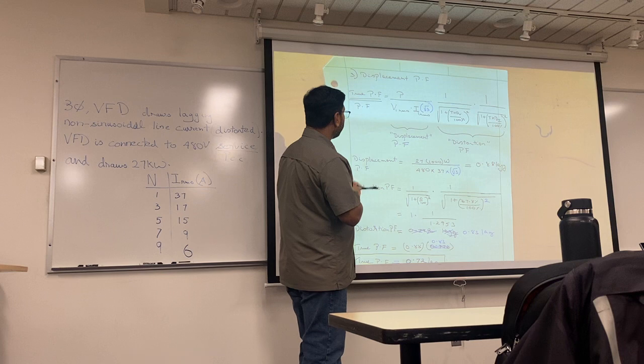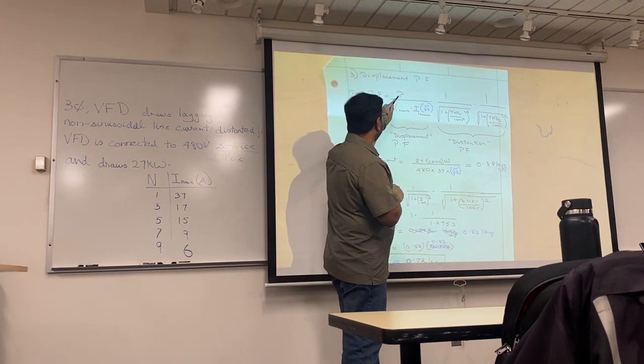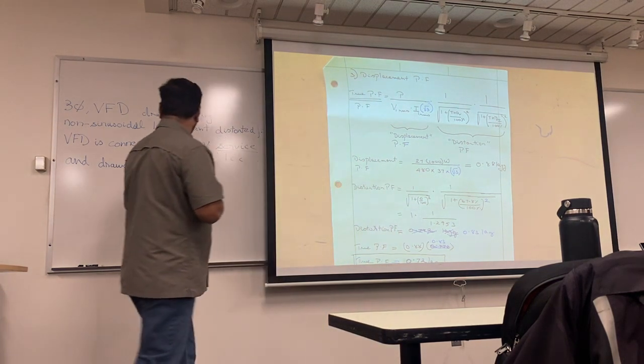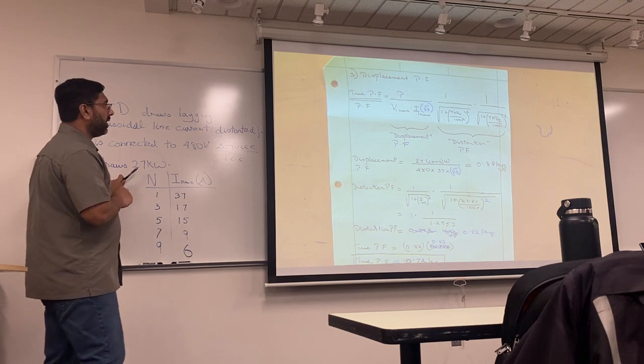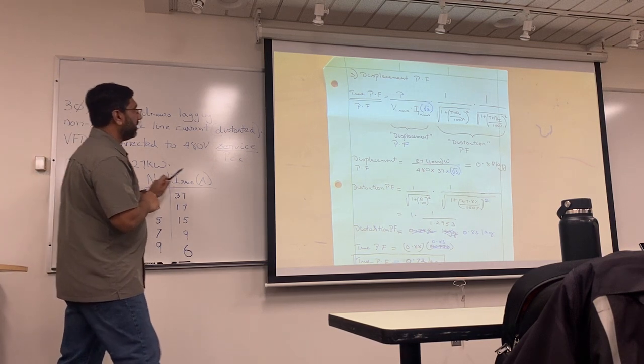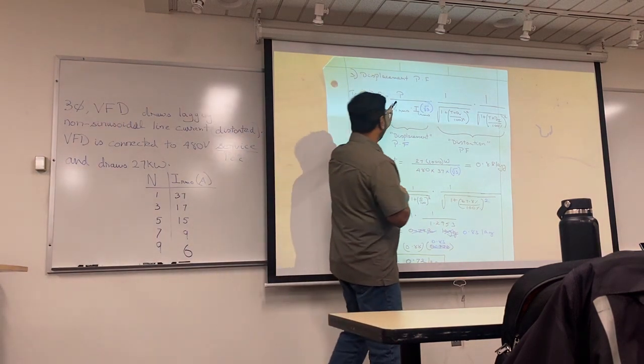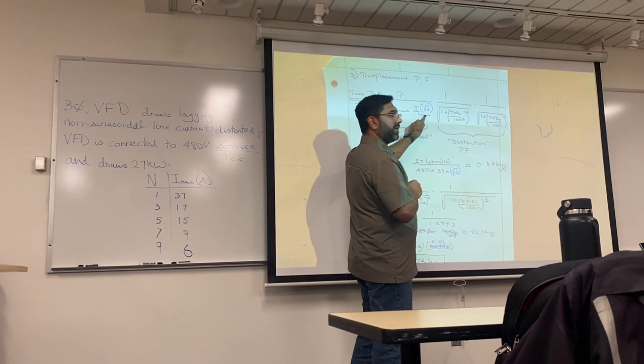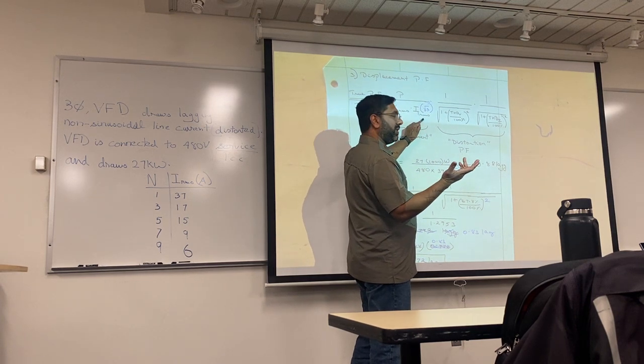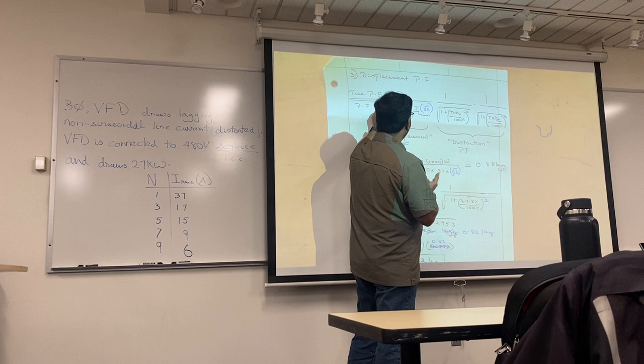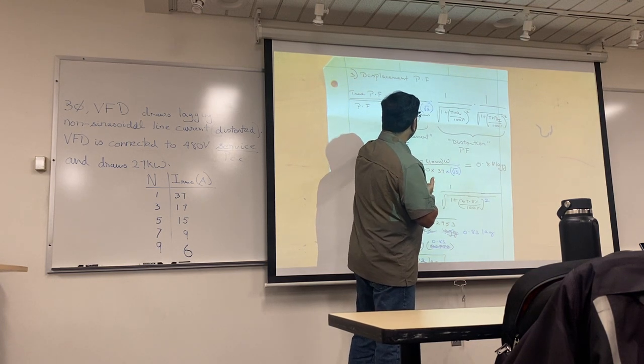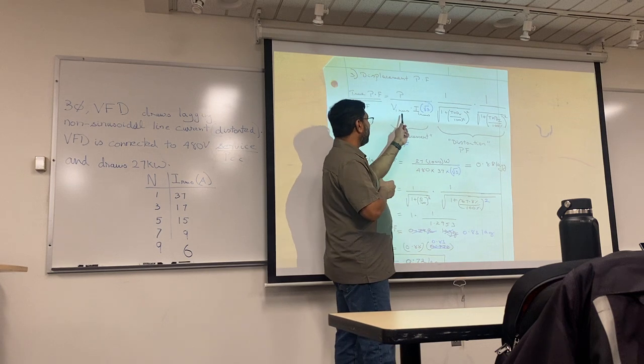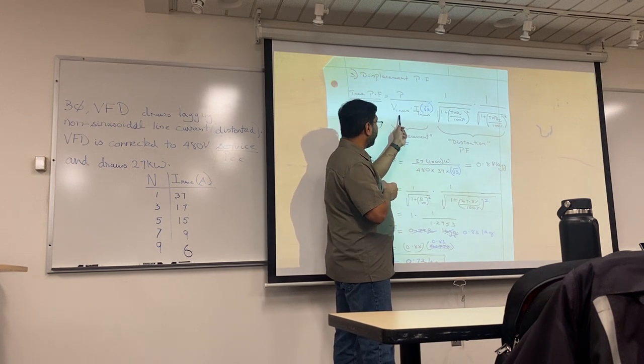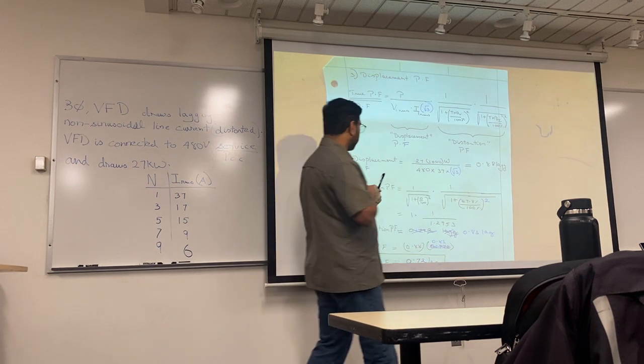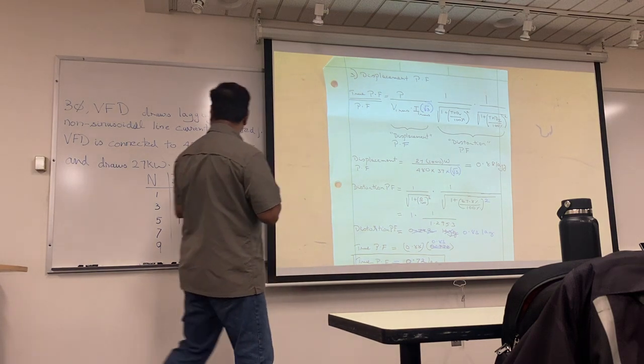I mentioned earlier we have 27 kW here, and this is 27 kW times root 3. At this point it should be clear why root 3 is used: your first harmonic voltage and first harmonic current. This is 480 volts, and I don't have a second harmonic on the voltage. This is the current I mentioned, I believe it's 37.